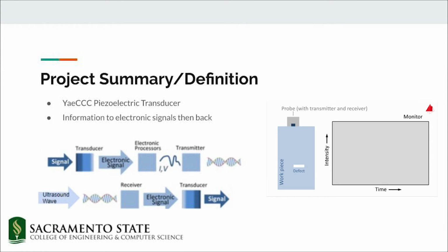This second image is illustrating the stages of the ultrasonic signal and what the transducer is doing. First, we begin with the transducer transmitting the ultrasound wave on the line, which gets recorded as a voltage. The wave then travels along and returns back to the transducer to get read and then finally converted back again to voltage. We will be able to use the information to search for fault locations on the line using wave reflection and comparing the ultrasound signals on both sides. This will give us exact locations of faults.